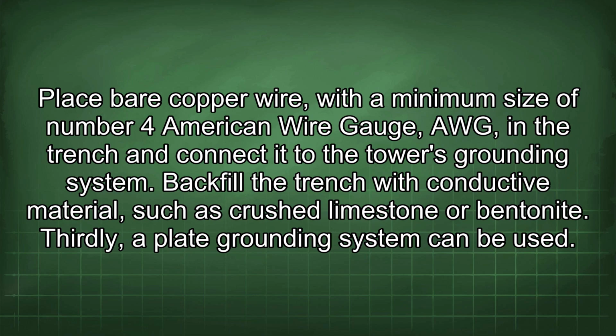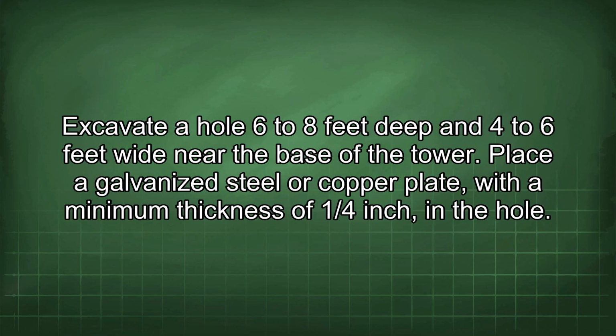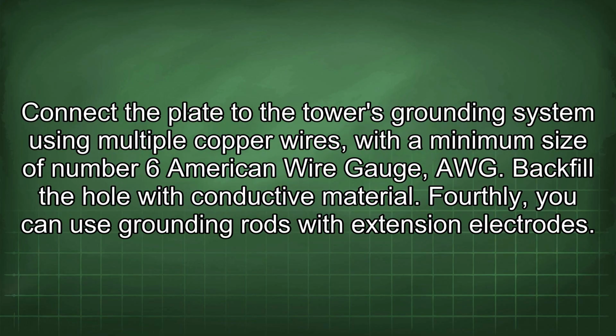Thirdly, a plate grounding system can be used. Excavate a hole 6 to 8 feet deep and 4 to 6 feet wide near the base of the tower. Place a galvanized steel or copper plate with a minimum thickness of 1/4 inch in the hole. Connect the plate to the tower's grounding system using multiple copper wires with a minimum size of number 6 American wire gauge, AWG. Backfill the hole with conductive material.